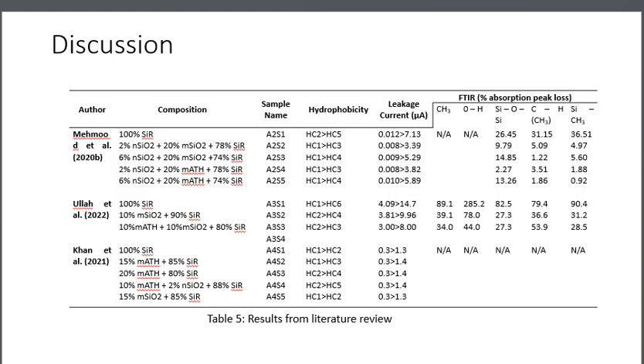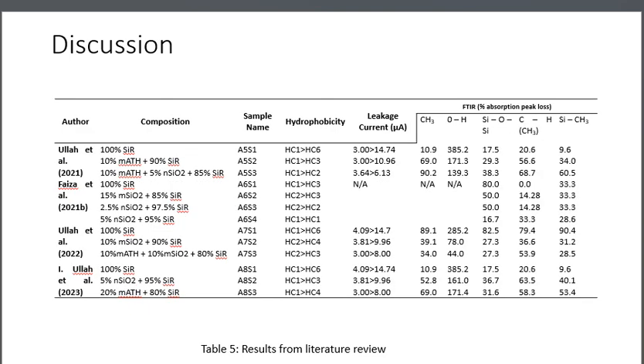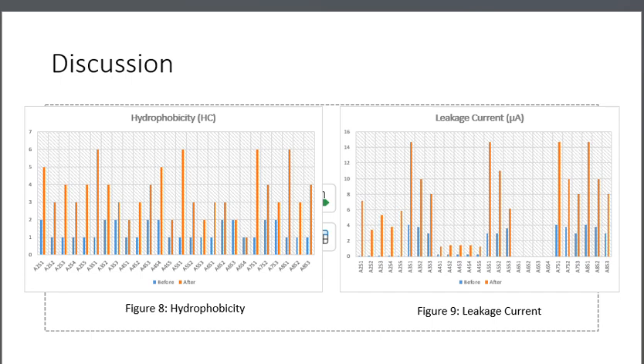Based on the literature reviewed, several key trends were identified. Hybrid coatings containing nano and microfillers containing SiO2 or silica and alumina trihydrate demonstrated improved performance compared to pure silicone rubber coatings. These improvements were observed across multiple performance indicators. First, regarding hydrophobicity, hybrid coatings showed better hydrophobic recovery after aging compared to pure silicone rubber. Second, leakage current values were significantly lower in hybrid filler samples. This improvement is linked to the coating's ability to maintain surface hydrophobicity and high surface resistivity.